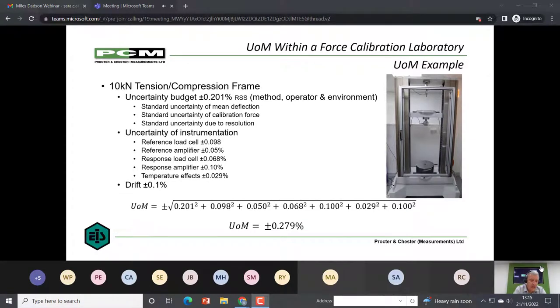And the last one is drift. It's a bit of, should we say, an afterthought add-in. It's more of an insurance for the calibration. If you combine all of these as the root of the sum of the squares, the actual uncertainty of the final calibration of that frame is just under 0.3%. Within our accreditation, that's listed at 0.3%, because going to three decimal resolutions like that is somewhat meaningless.